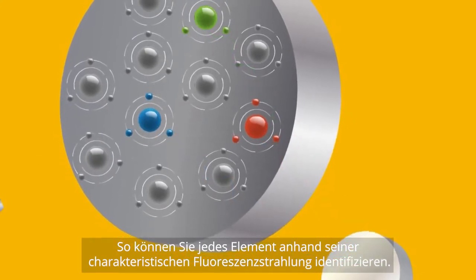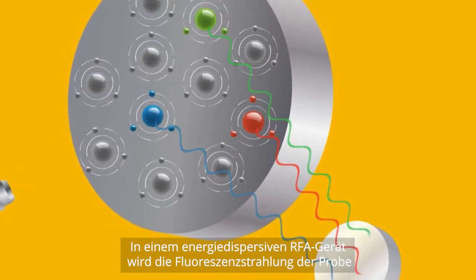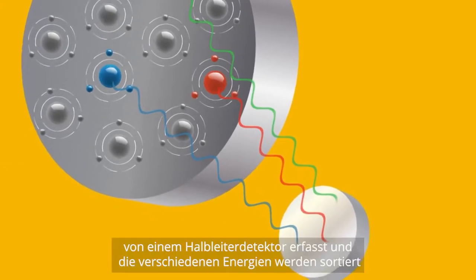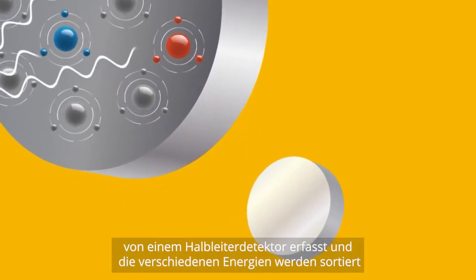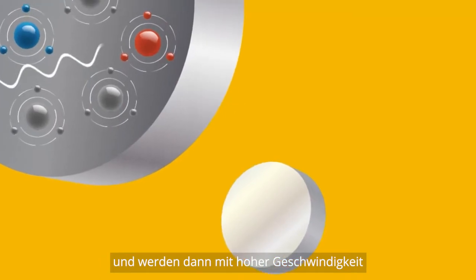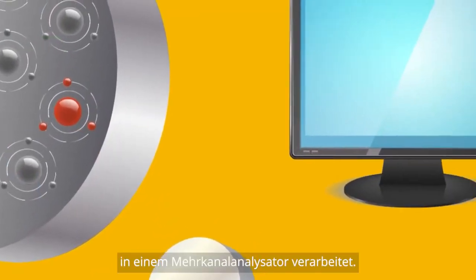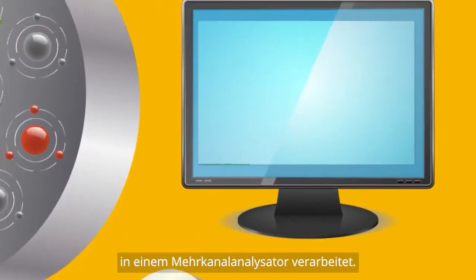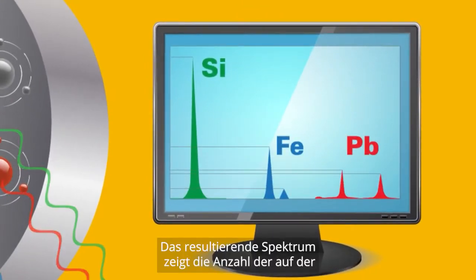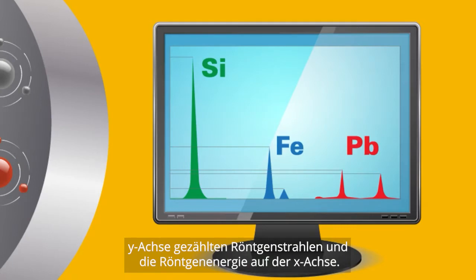That energy difference is unique for every element, so you can identify each element by its characteristic fluorescence radiation. In an energy dispersive XRF instrument, the fluorescence radiation from the sample is collected by a semiconductor detector, and the different energies are sorted and processed at high speed in a multi-channel analyzer. The resulting spectrum shows the number of X-rays counted on the Y-axis and the X-ray energy on the X-axis.